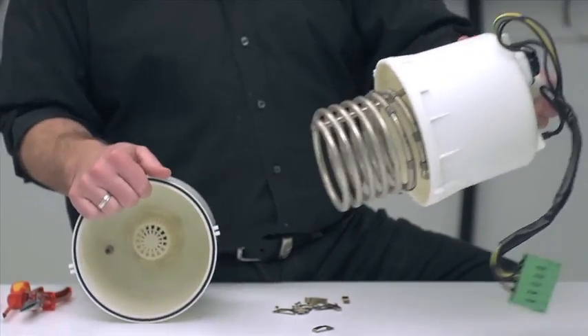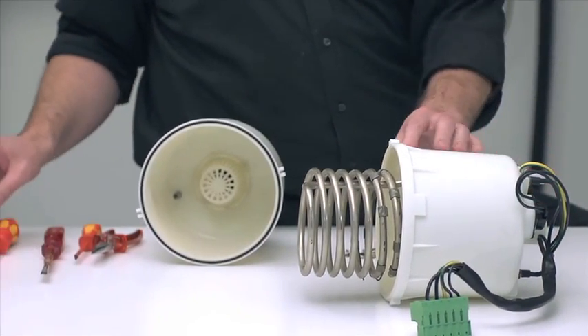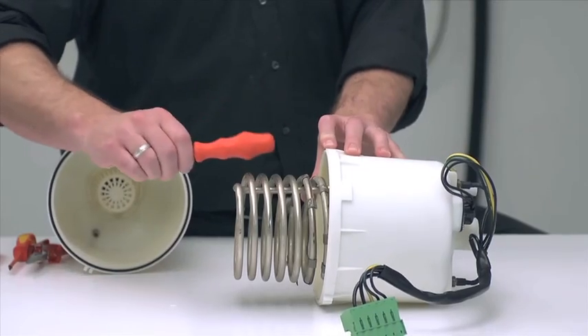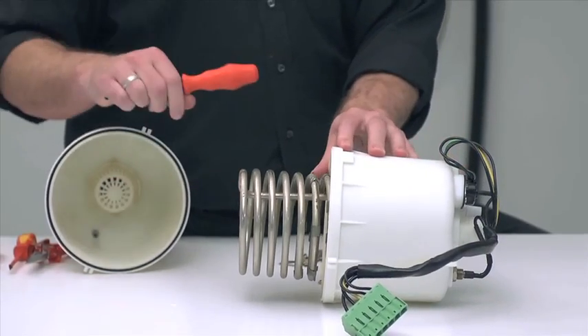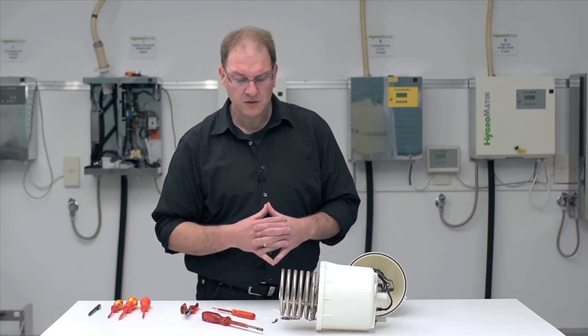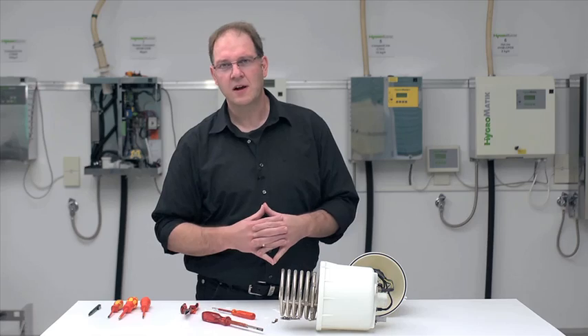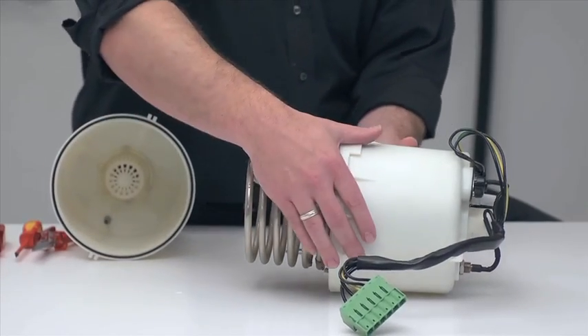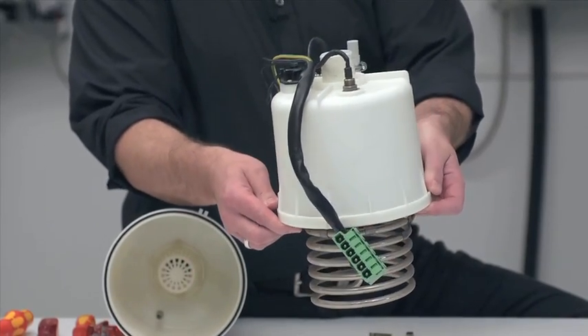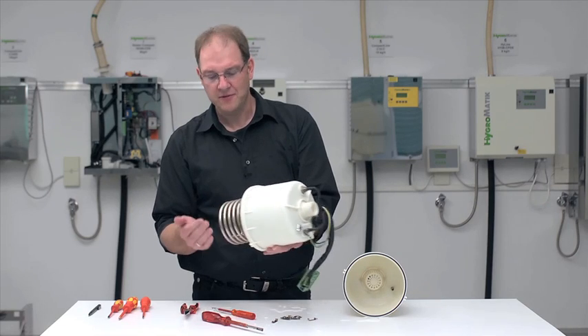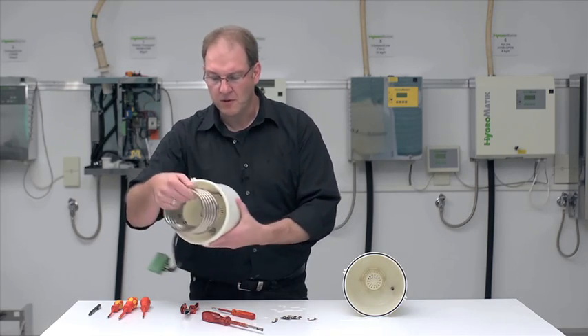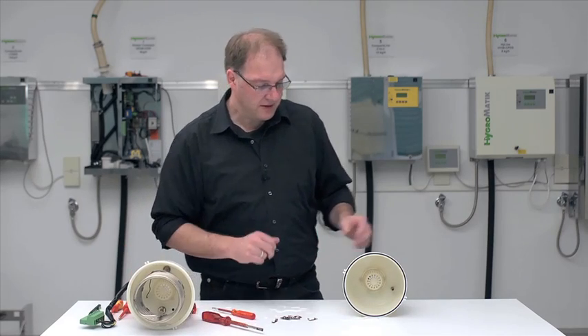And now for cleaning, I would first check how much deposit is on it. If there is a light coating of mineral deposits, I would try to go about it with a screwdriver. I use the shaft of a screwdriver. Knock around on the heater element a bit, not too hard, you don't want it to bend, and then small pieces of scale will chip off. In case none of that is very effective, then it would be sensible to immerse the whole thing in cleaning agents that have a certain acid content, not above 10%. Then I can, when I have prepared such an acid bath, just place the whole cylinder inside, so that the heating element is immersed in the bath. But please, not the electrical connections up top, they couldn't take it. How long you need to allow for it to soak depends on the amount of deposit coating it, how thick the layer is, how strong the cleanser is. That would be all concerning the cleansing of the heating element.